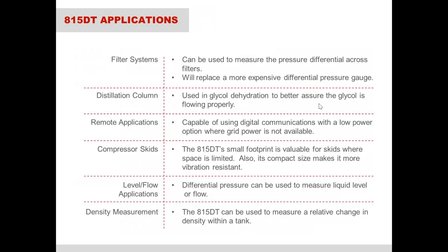The 815DT has a lot of different applications. One of the common applications is monitoring the life of filter systems. When you measure the differential pressure across the filter, there's a drop in pressure, and the higher the drop in pressure, the more clogged up that filter is. With a differential pressure transmitter on there, you can monitor the life of that filter and know when it's time to replace it.